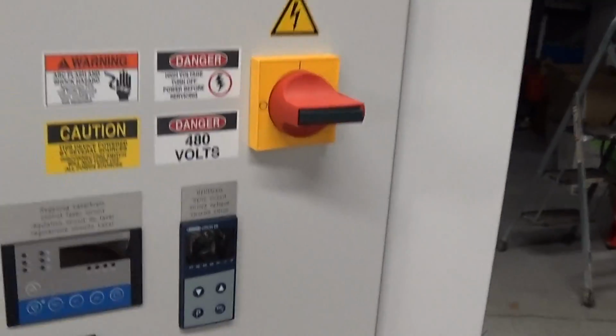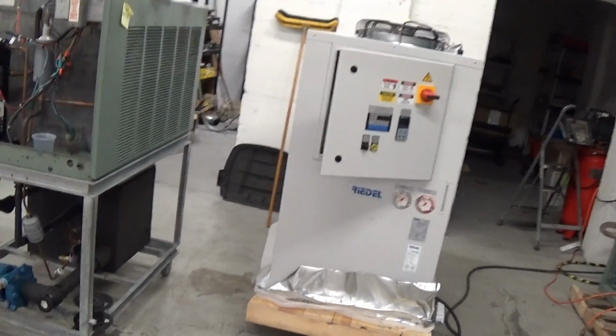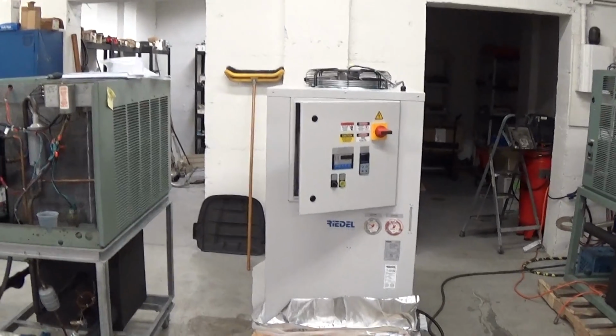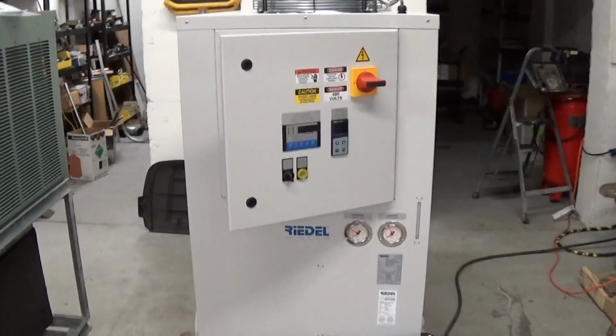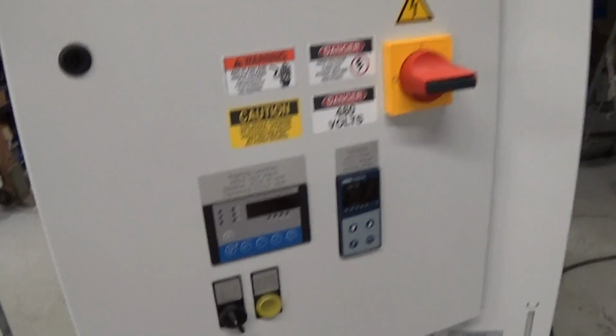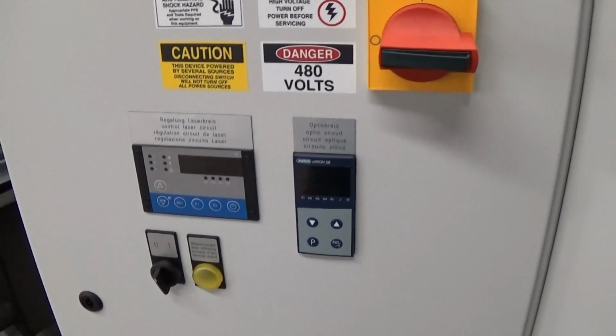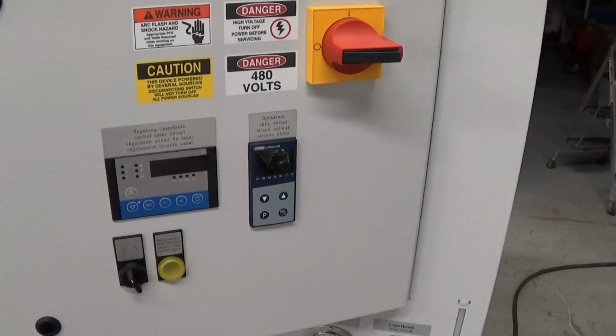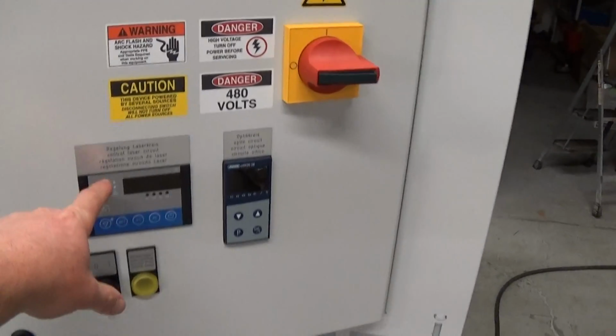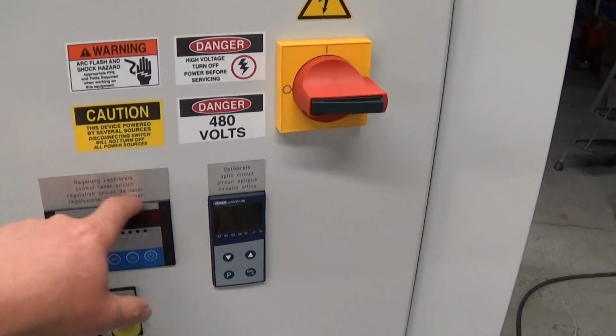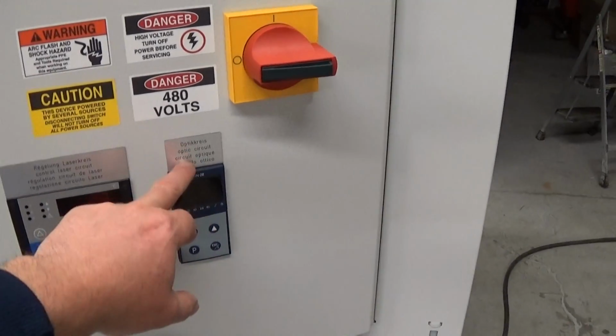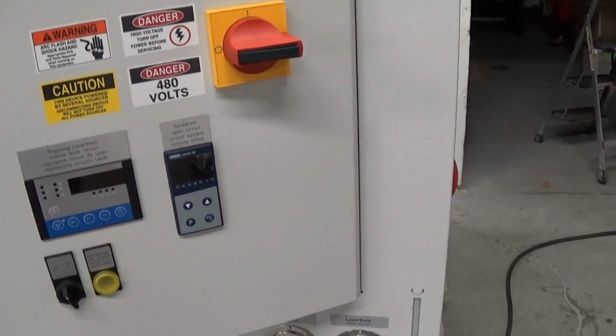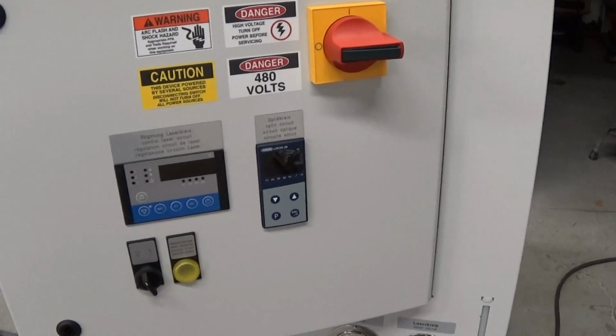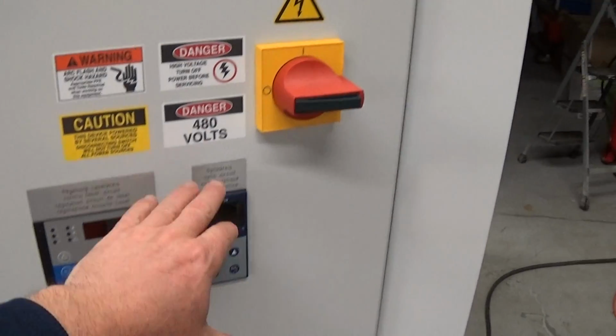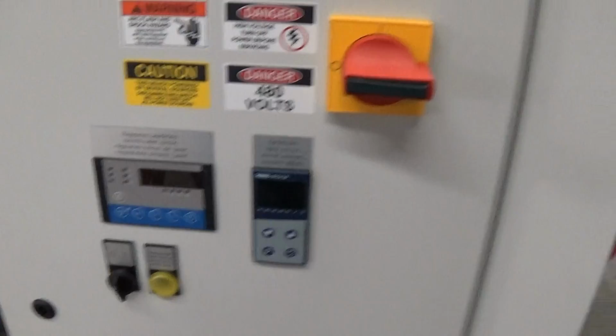This unit, and as we're talking, let's turn off our heater here. This unit is a 460 volt 3-phase. Now these units, and we've done this many times, were originally set up for a laser machine and for 2 circuits, where the main circuit, which is run by this controller, controls the laser circuit. This circuit here is what they call an optic circuit, which is about 10% or 5% of the water flow of the whole unit. What we do is we basically disable this whole circuit here because we don't need it for 99% of the applications that our customers use these for.